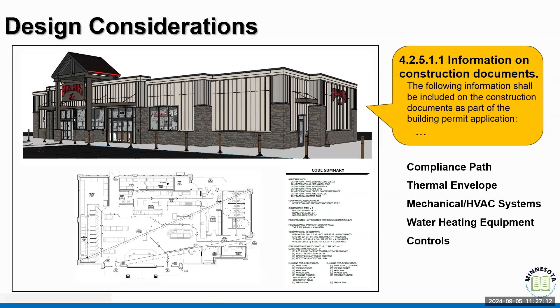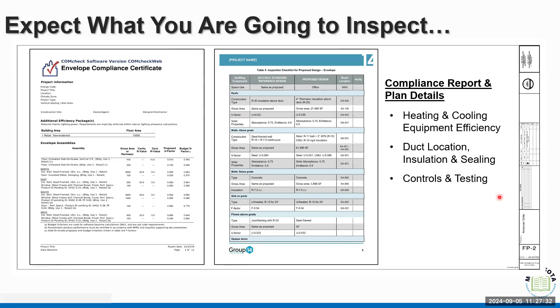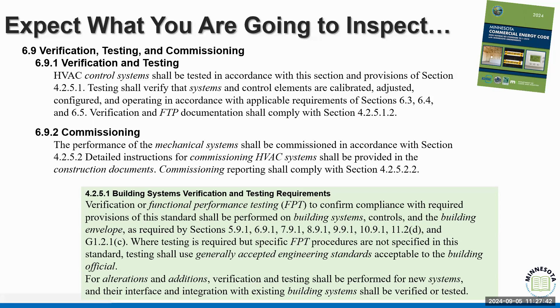Part of that flexibility is understanding what we're going to inspect and what we're expecting to see when we inspect. Sometimes we get a nice little COMcheck, or an energy report that tells us what we should see as far as equipment efficiency expectations, duct insulation, locations, and sealing details—again, controls and commissioning. Remember, the code requires that we identify functional testing requirements so that from the beginning there's a methodology for commissioning the equipment.